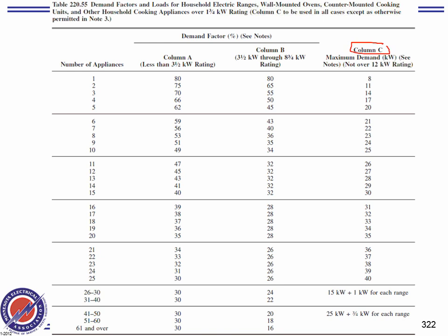Always. By the way, when would you use this table? You use this table not for Perkins and McDonald's and all these fast food restaurants or non-fast food. You use it for dwellings, apartments, and single multi-family dwellings only. For the ranges and wall-mounted ovens and counter-mounted cooking units, anything related to the cooking. Suppose I have 15 apartments and each one of them has a range. The demand for 15 apartments is 30 from the get-go. 15 ranges, the demand is 30.